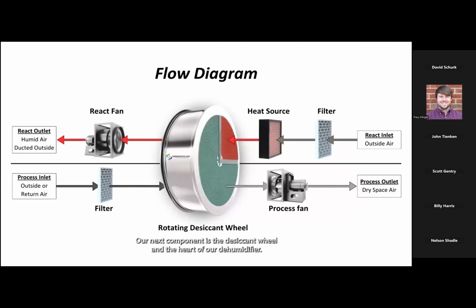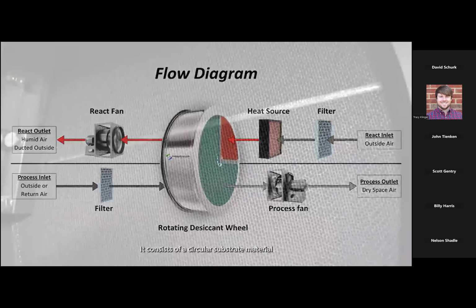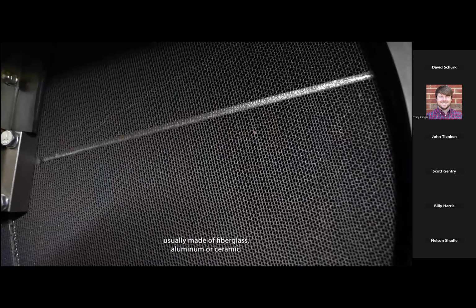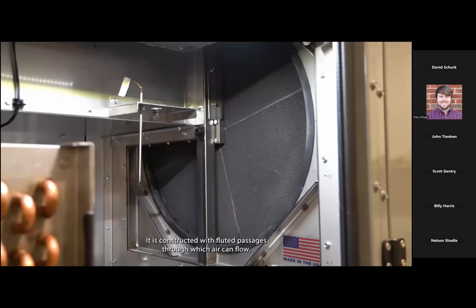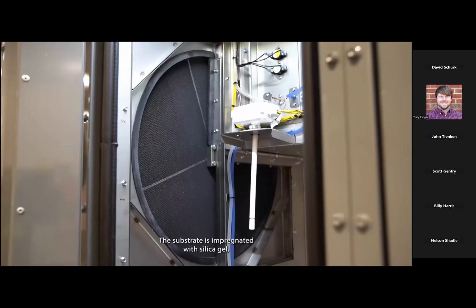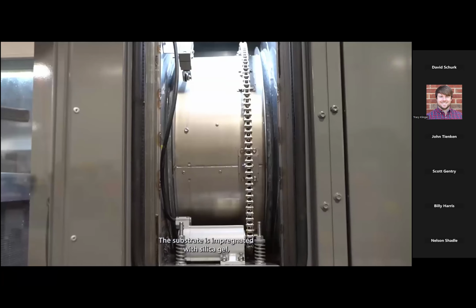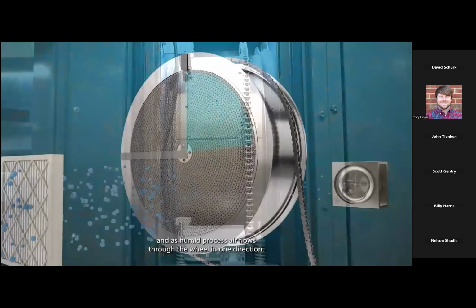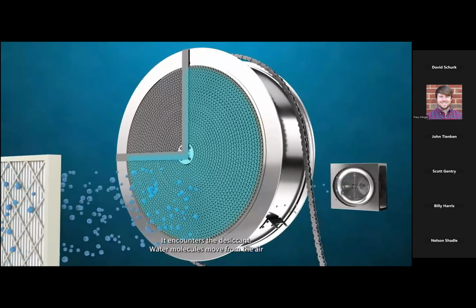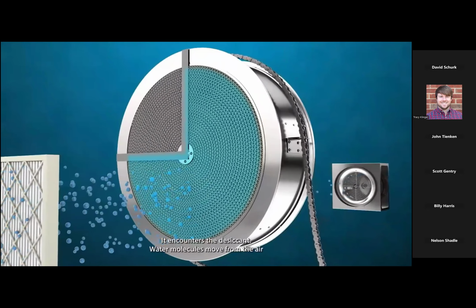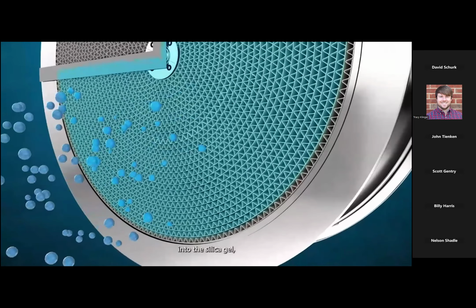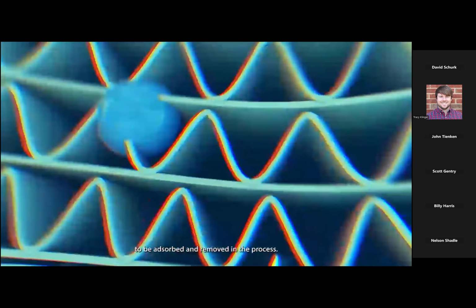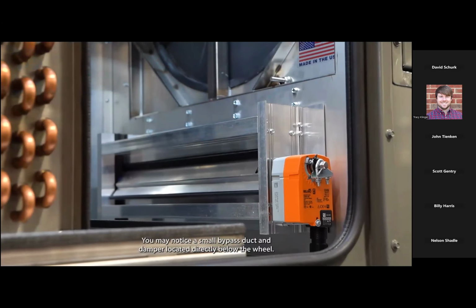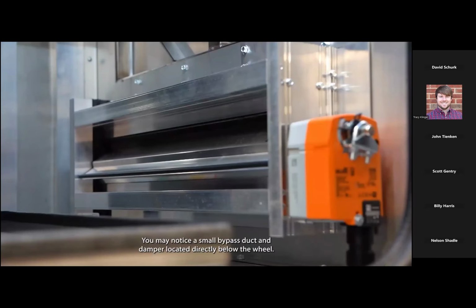Our next component is the desiccant wheel and the heart of our dehumidifier. It consists of a circular substrate material, usually made of fiberglass, aluminum, or ceramic. It is constructed with fluted passages through which air can flow. The substrate is impregnated with silica gel, and as humid process air flows through the wheel in one direction, it encounters the desiccant. Water molecules move from the air into the silica gel to be adsorbed and removed in the process. You may notice a small bypass duct and damper located directly below the wheel.